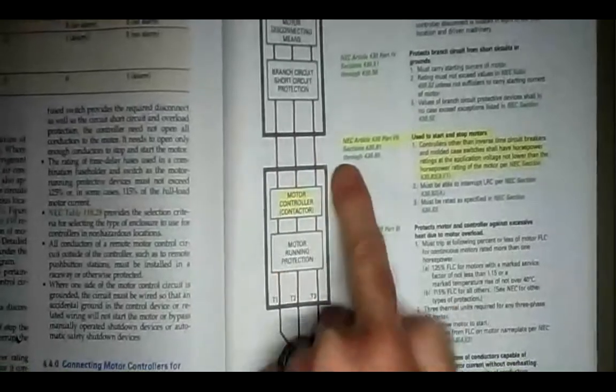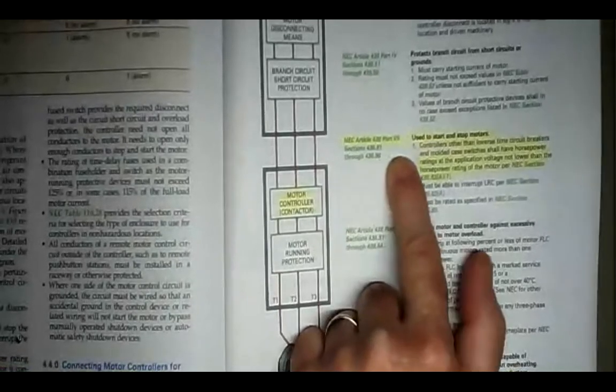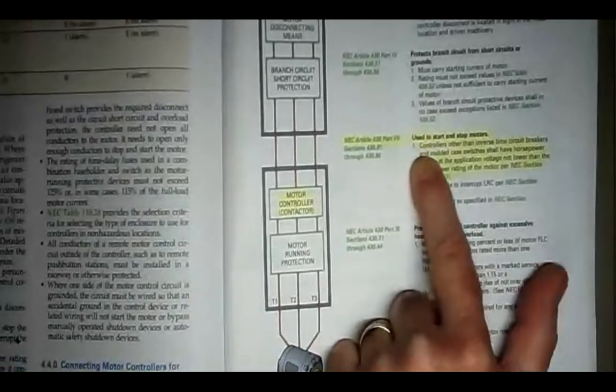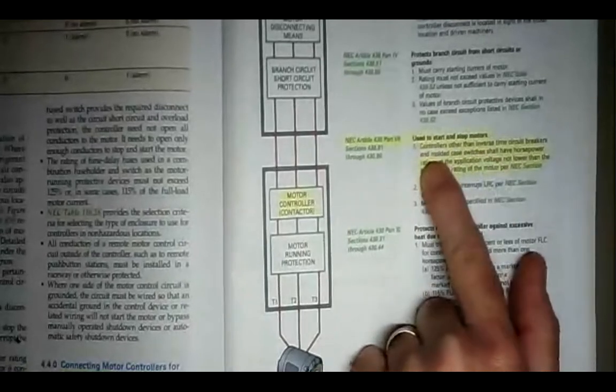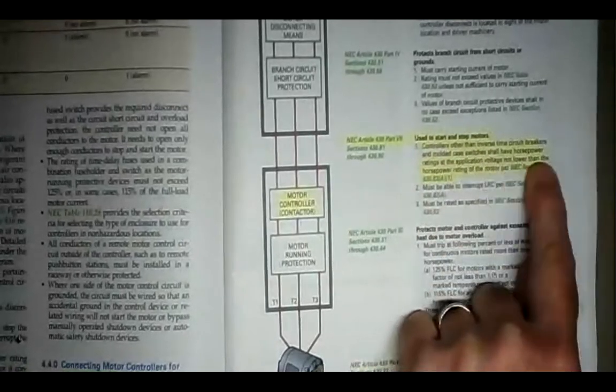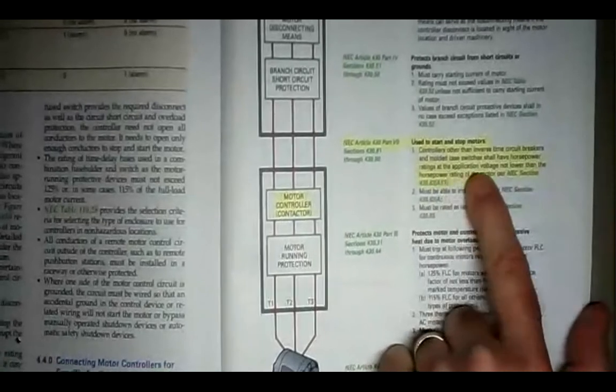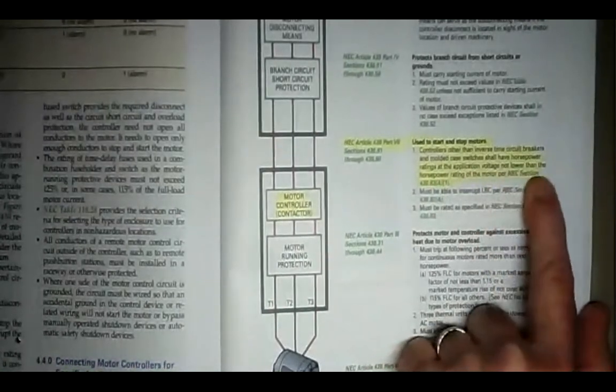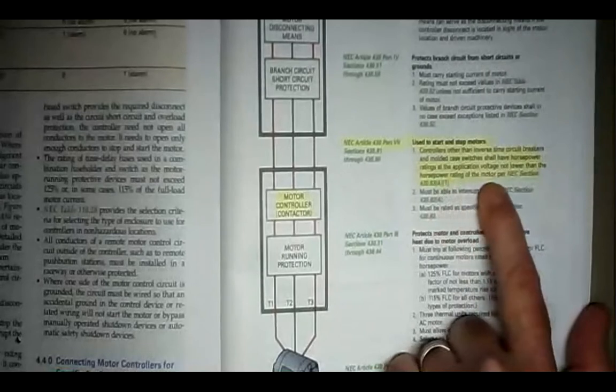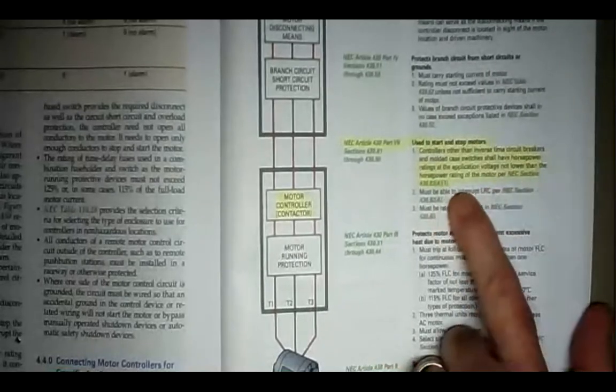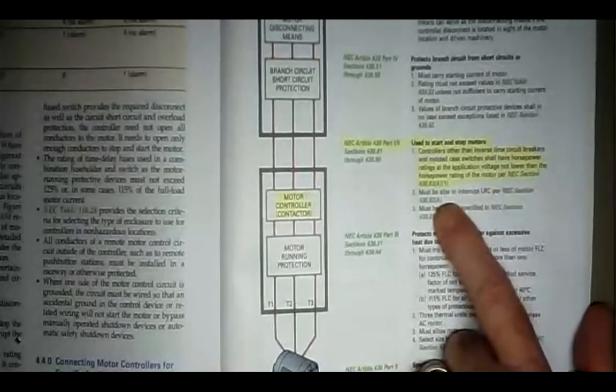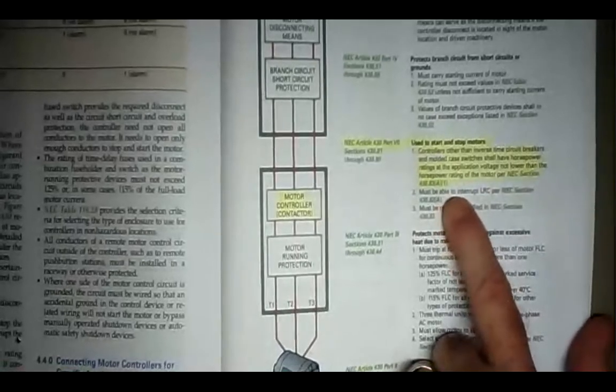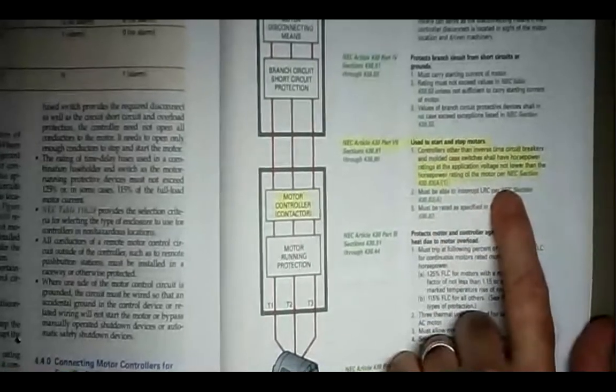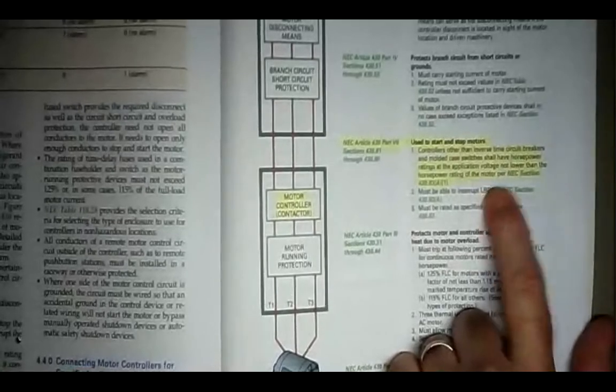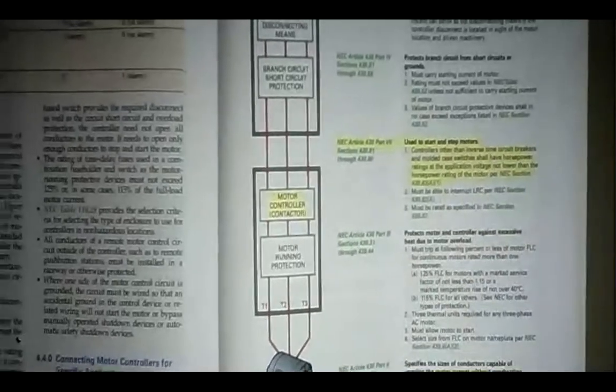and of the contactor. NEC Article 430 Part 7 tells us they're used to start and stop motors. Controllers other than inverse time circuit breakers and molded case switches shall have a horsepower rating at the application voltage not lower than the horsepower rating of the motor per NEC section 430-83A1. So they have to be rated in horsepower, and it has to have a rating at least that of the motor nameplate. Okay.